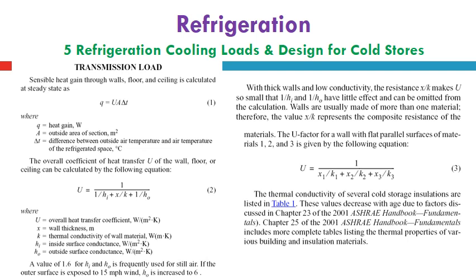The U factor for the wall with flat parallel surfaces of materials 1, 2 and 3 is given by the following equation. To consider the composite wall overall heat transfer coefficient in watt per square meter Kelvin, U will equal 1 over x1 over k1 plus x2 over k2 plus x3 over k3. The thermal conductivity of several cold storage insulations is listed in Table 1, which will be presented in the next slide.